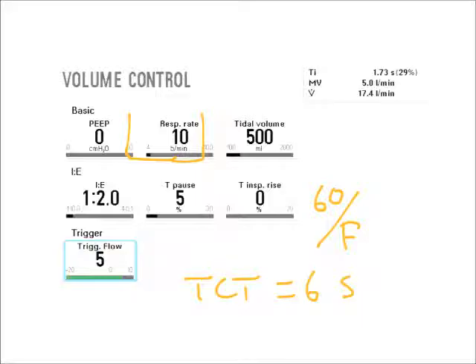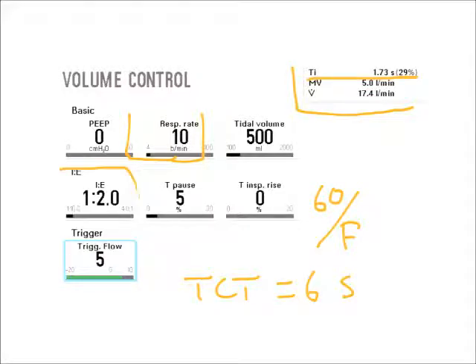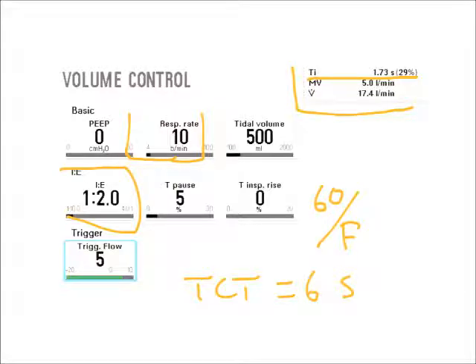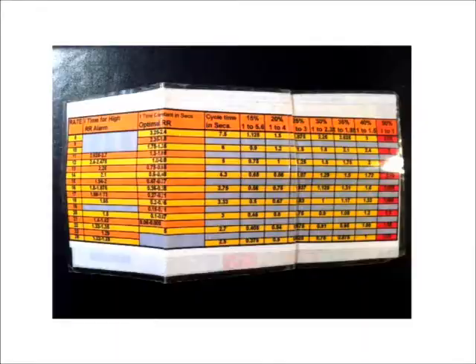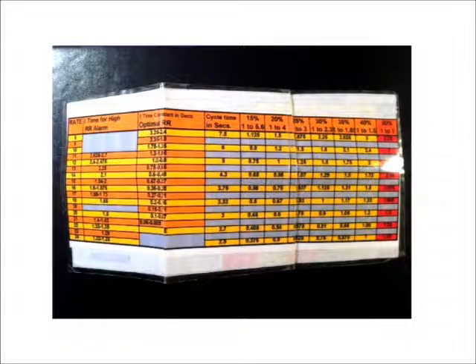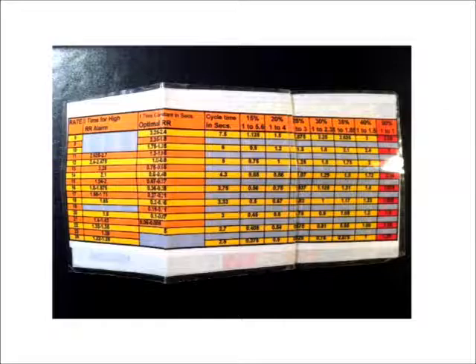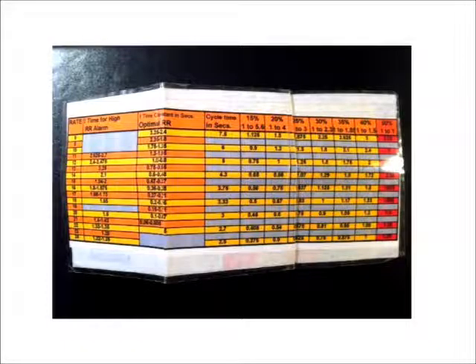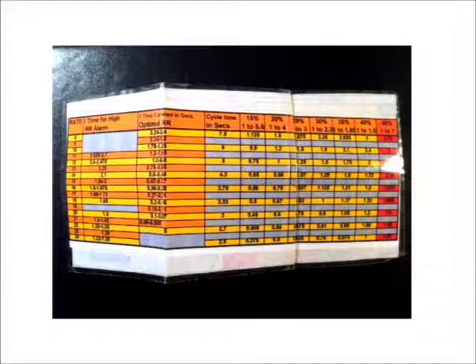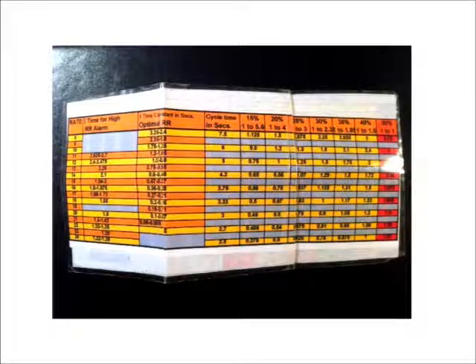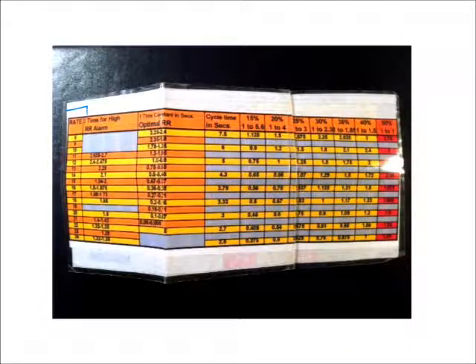Now newer machines, as you notice, newer ventilators have these little smart windows. Here's an example of a smart window right here that already calculates my inspiratory time, and that's also based on my I:E ratio. Some older ventilators don't have that. What's kind of nice is if you have a cheat sheet or a cheat chart, and this is what I have for setting up my MRI vents or ventilators, so I can know what the inspiratory time is and the total cycle time and everything else. I'm going to go over this nice little chart here.